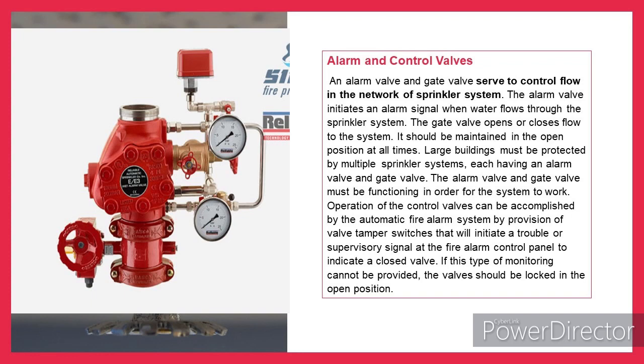Large buildings must be protected by multiple sprinkler systems, each having an alarm valve and gate valve. The alarm valve and gate valve must be functioning in order for the system to work. Operation of the control valves can be accomplished by the automatic fire alarm system by provision of valve tamper switches that will initiate a trouble or supervisory signal at the fire alarm control panel to indicate a closed valve.